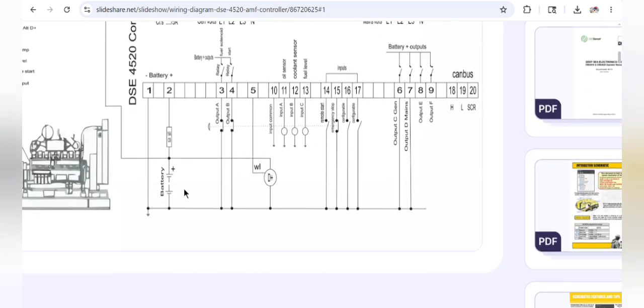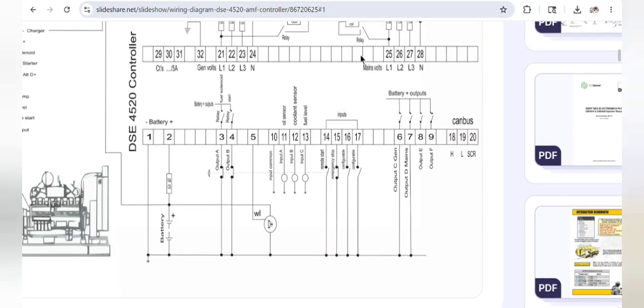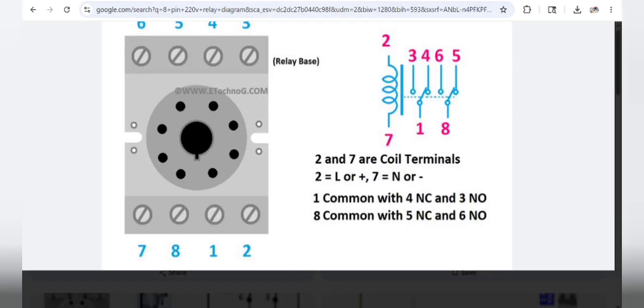As you can see here, from pin 1, this is our ground feed to pin 14. This is a normally open contact. When this goes to normally closed, the generator receives the ground remote signal, and the generator will start automatically through this ground signal fed to pin 14. Understand? So let's move to the relay diagram, how to install the remote start signal to this controller to start the genset automatically and shift the load.